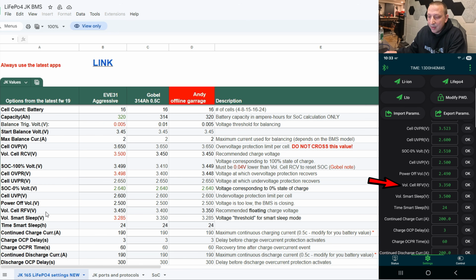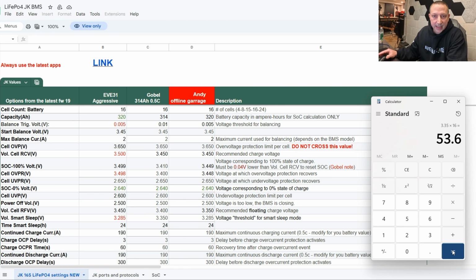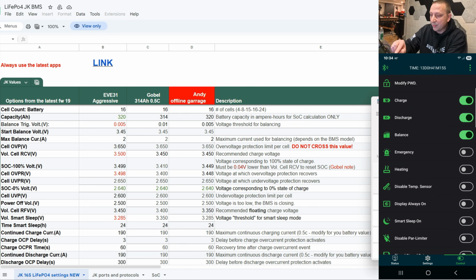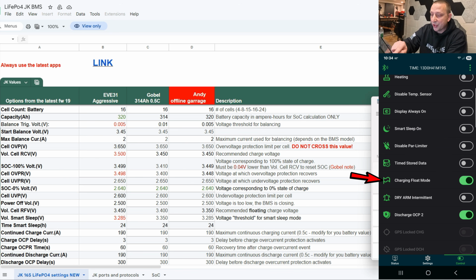The next one down is the voltage cell RFV. If we look at this sheet, it says the recommended float charge voltage. Everybody says 3.45 or 3.4, and Andy recommends 3.35. If we do 3.35 times 16, the reason we leave it at that is because whenever you fully charge a battery or cell up to 3.65 volts and let it rest, its natural resting voltage is going to be that 3.35. So times 16, our float voltage is 53.6 volts. Andy goes through all of these in great detail. You come to this page for control, and there's a charge float mode here you can turn on or off if you want to use that option. Those two settings kind of go back and forth with each other.